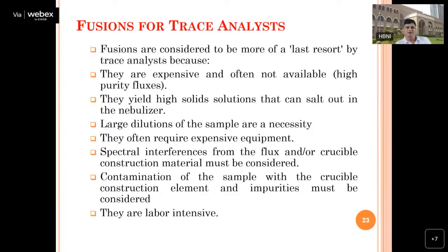So they are expensive and not available, and they yield high solid content. As I told you, the salt content actually always chokes my nebulizer, because ultimately before putting this solution into any kind of instrumentation, it has to be turned into tiny droplets with the help of a nebulizer. So those nebulizers get choked when we have a very high salt content.